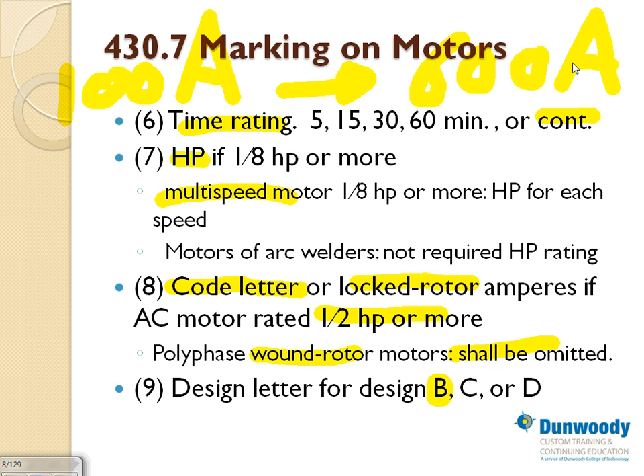Who cares? Have you seen sometimes an air conditioning kicks in and the lights dim down, right? That's because we're pulling so much current, it creates a big voltage dip in the system, and the lights got a smaller amount of voltage across them, so they went down momentarily, and then they come back up. That's bad news for the electrical system, so we're going to reduce it. That's as a function of the code letter.